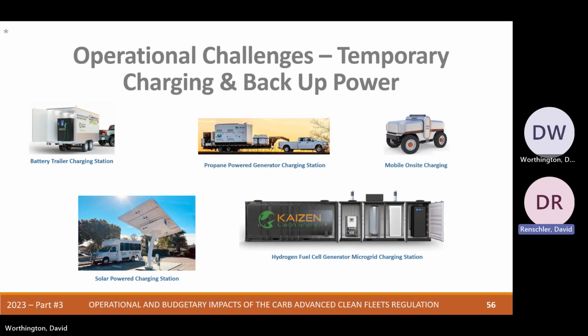However, we found some challenges with this. One, it was cheaper - 1.3 million - and we can charge 2 buses with it. The challenge we're running into now is getting a permit to operate it. Even though it's portable, and you'd think it would be under the portable equipment registration program, our air district doesn't allow that because it's going to be in one place. We need to get an authority to construct and a permit to operate, just like a normal stationary generator.